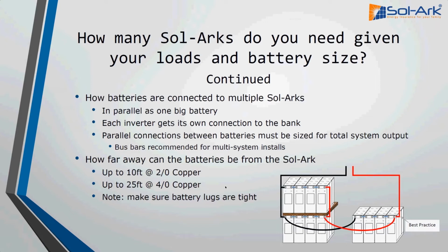When you're connecting your batteries to the Sol-Ark, if you have parallel Sol-Arks, you need to have one big battery bank, and then each inverter gets its own connection to that large battery bank. You also need to make sure that your connections between groups of batteries in your battery bank are sized appropriately, so they can handle the current of all the systems connected. Once you get up to 2, 3, 4 systems, you pretty much have to use bus bars to get the current ratings required.